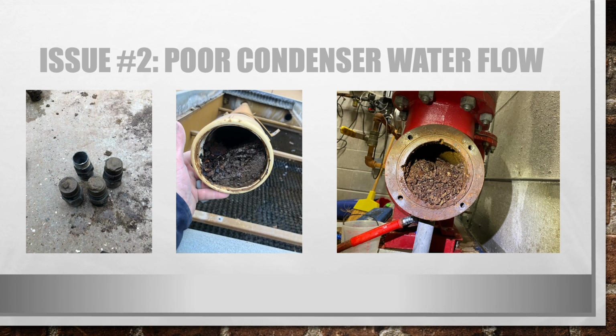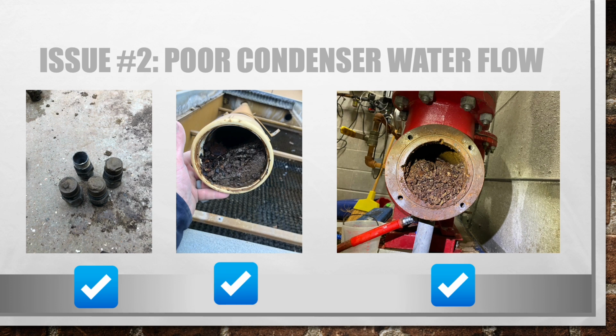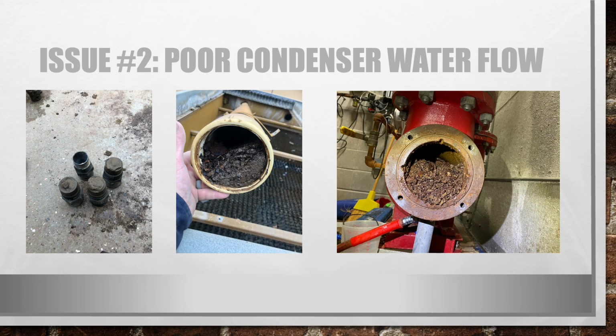So one of the things I would say, the first place you should be looking is going to be the screens in the system. So pull all the screens, check all the screens, make sure none of them are fouled up. The next thing you can check is all the tower nozzles. Make sure the tower nozzles and the headers are all clear. Make sure there's no rust chips in there. Make sure there's no gunk in there. And then sometimes rust chips or cooling tower media or things like that might get lodged in the entering side of the condenser, so that can get fouled up as well, but you shouldn't be checking that till the very end. So check your tower nozzles, check your screens, make sure everything's clean.